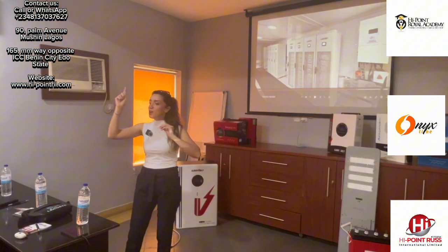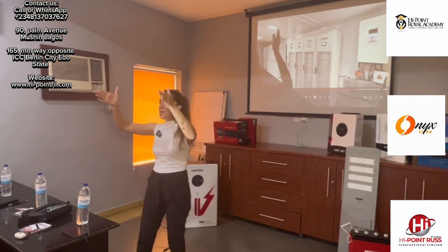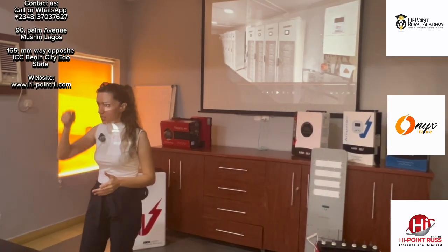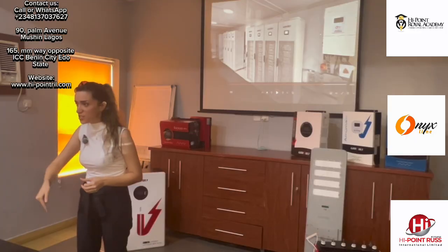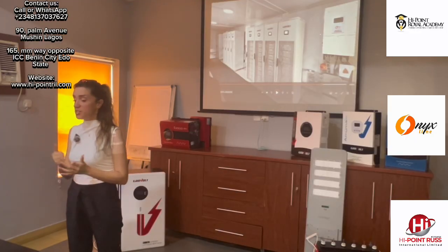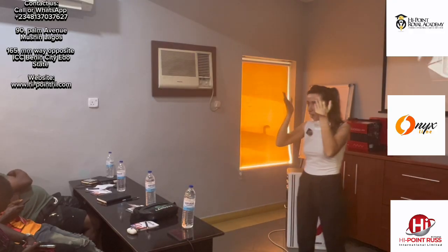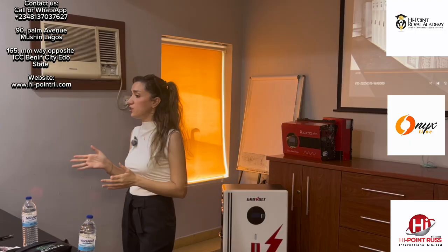Guys, I have one question. Inside this cabinet, I have 10 battery. This battery, is it connected in series or in parallel? In series, okay. So the voltage for this battery, how much? I said each battery is 5 kilo, 51.2 volt. 512 volts. That means we are in a high voltage battery. Each cabinet is 512 volts.